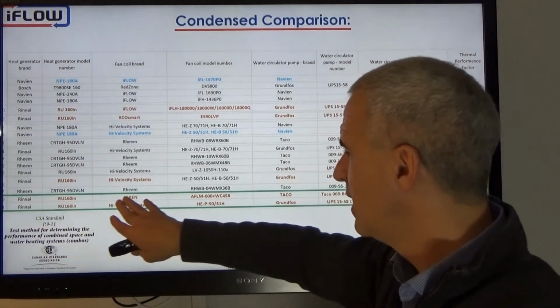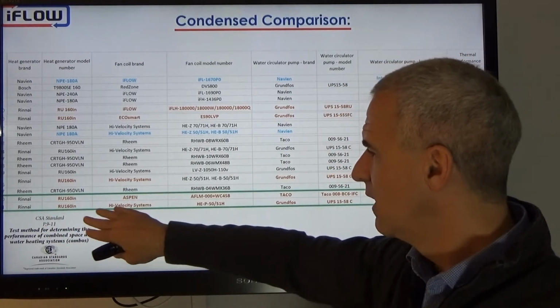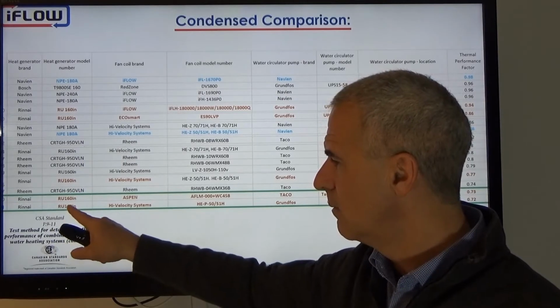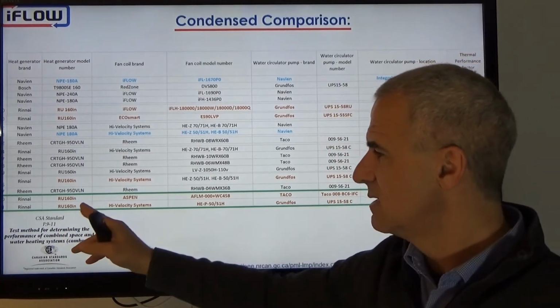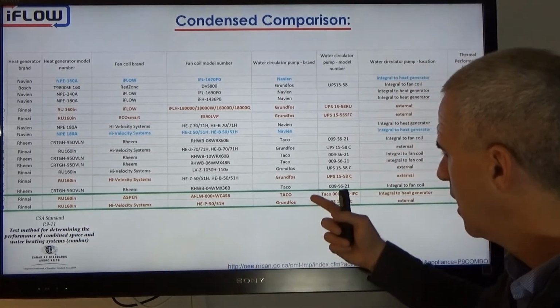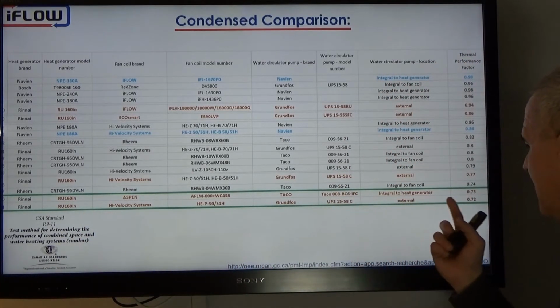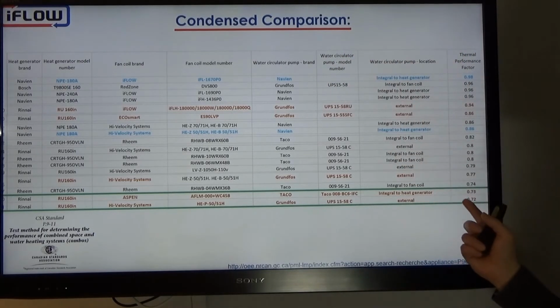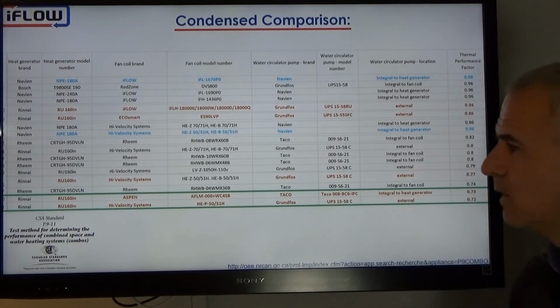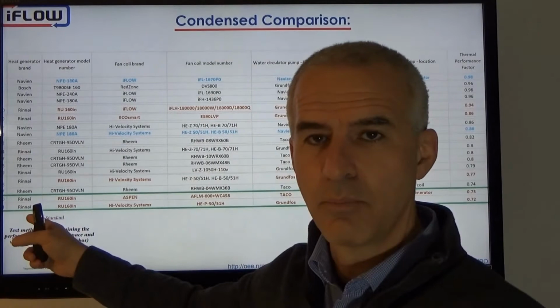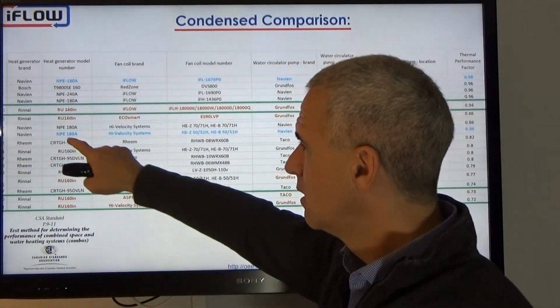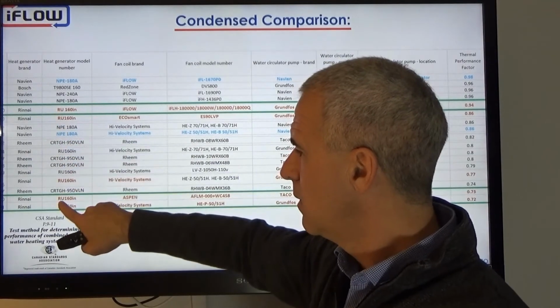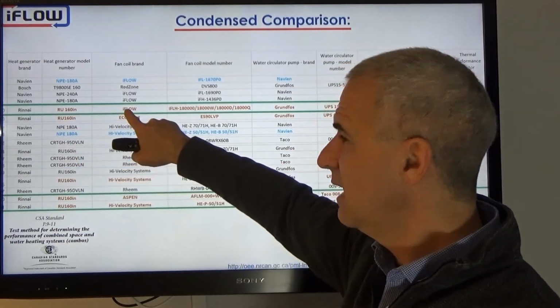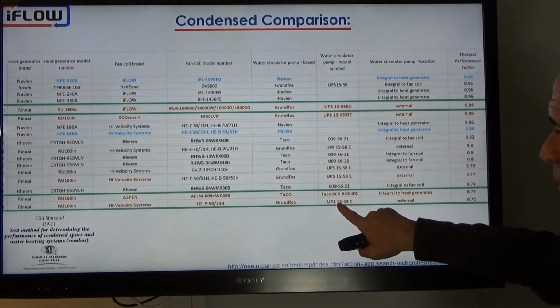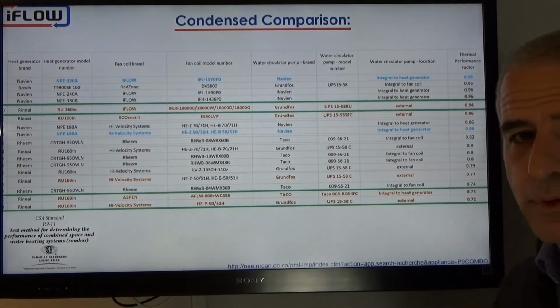So we have Aspen and we have high velocity that both tested with the Rinnai RU160IN. This is their Sensei model, 160,000 BTUs with, let's say, a Grundfos 1558, and they scored on the Canadian CSA P9 standard a 0.72. The Aspen scored a 0.73 with the Rinnai. So you would say, wow, the Rinnai didn't perform very well. Well, no. Look at the Rinnai with the iFLOW. The same RU160IN tested with the iFLOW with the same Grundfos 1558 scored a 94%.